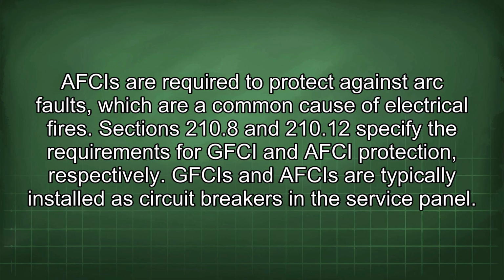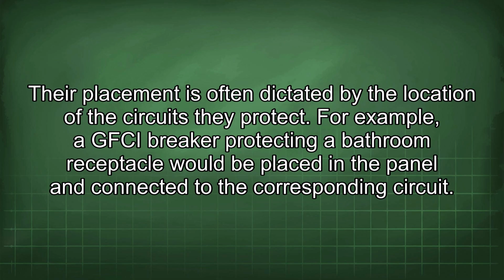AFCIs are required to protect against arc faults, which are a common cause of electrical fires. Sections 210.8 and 210.12 specify the requirements for GFCI and AFCI protection, respectively. GFCIs and AFCIs are typically installed as circuit breakers in the service panel. Their placement is often dictated by the location of the circuits they protect.